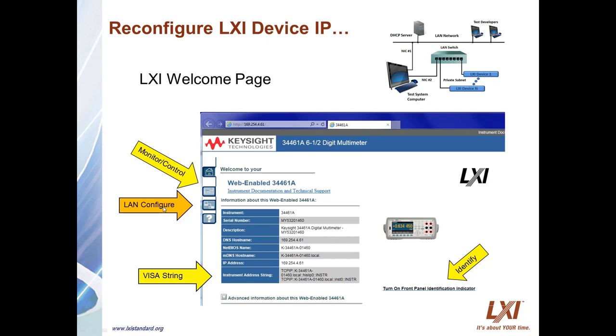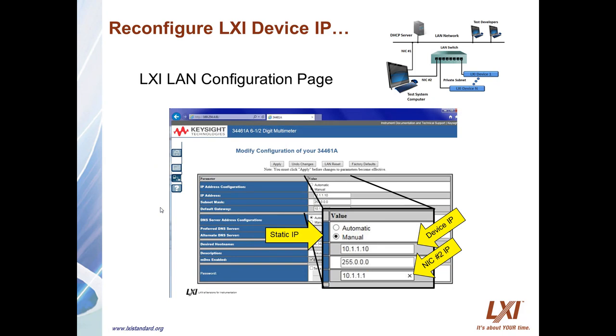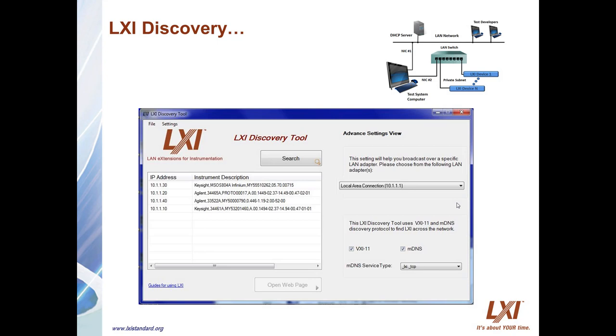The LAN Configure section is where we go to change the IP address of an LXI device. The device is shipped configured for automatic or DHCP. To make the address static, choose manual control on the configuration web page. The gateway's NIC number two address is placed as the default gateway for access back to the interface card. In this case, we assign an IP address of 10.1.1.x with a subnet mask of 255 — the same subnet as the network interface card. Repeating this for each LXI device means all devices are on the same subnet as NIC number two, using static and easy-to-document IP addresses.